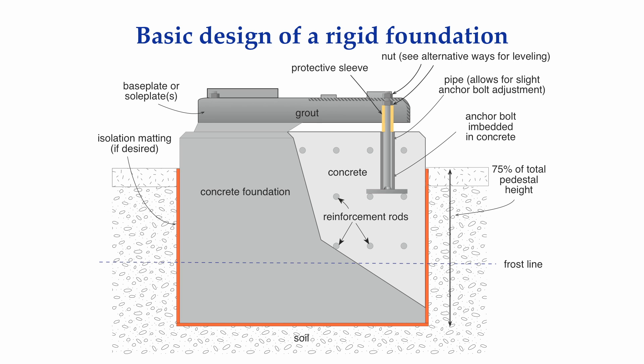The grout is allowed to cure and the form is removed. After adequate curing time, the rotating machinery is then set on top of the base plate or sole plates or chock plates. This is the most stable platform for rotating machinery and is extensively used in industry. A more detailed discussion on foundation design, leveling of base plates and sole plates, and grouting will be discussed in another tutorial.